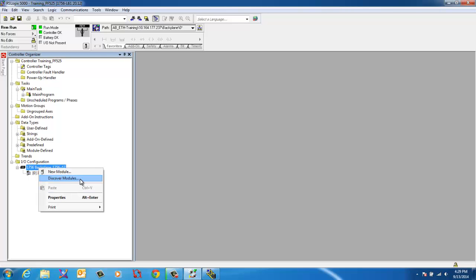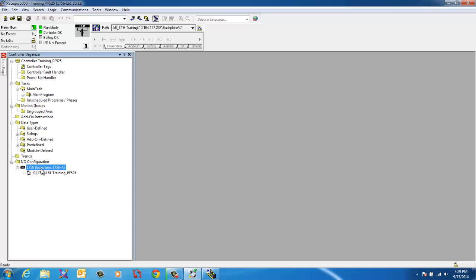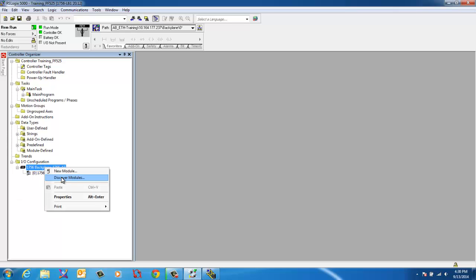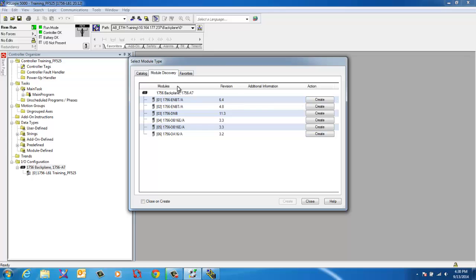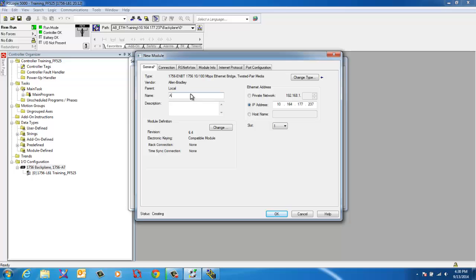Alright, we're going to do module discovery. So in your IO tree, we're going to add it. We need to add it to our network card. But we're going to do this a little different. We're going to have an automation network and then we're going to have a private network. We're going to add the PowerFlex drive to our private network. Module discovery. You can do this while you're online. Populates a list of everything that I have in here. I've got two Ethernet cards and a DeviceNet card, some output cards. We're only going to worry about these two. So we'll go ahead and create this one. We're going to call this the automation network. Because this is the one that's on your factory floor. And the nice thing about doing the module discovery is it populates everything that you already have. You don't have to change anything. It puts the IP address that's already in it. That's all we need.